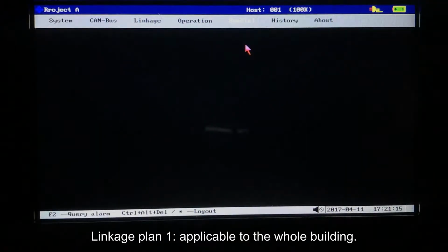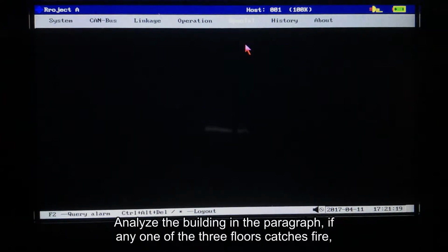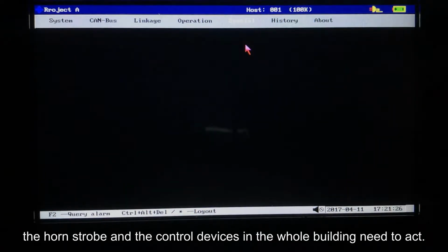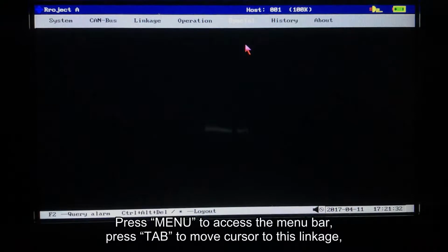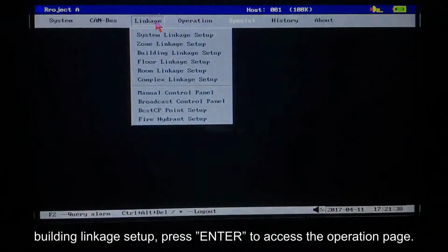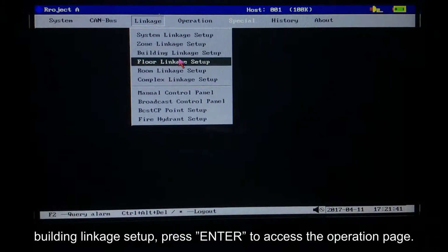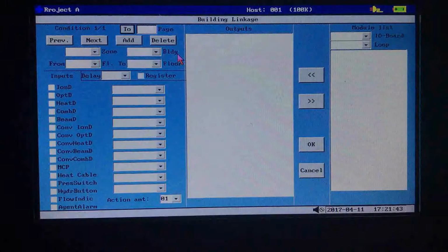Linkage Plan 1, applicable to the whole building. Analyze the building in the paragraph. If any one of the 3 floors catches fire, the horn strobes and the control devices in the whole building need to act. Press Menu to access the menu bar. Press Tab to move the cursor to this linkage. Building linkage setup. Press Enter to access the operation page.